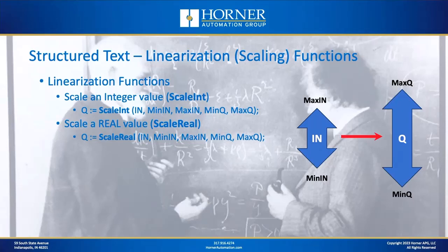So, of course, you can use y equals mx plus b scaling, and we'll show you an example of how to do that. But there also are some specific purpose scale functions available for you to use. There's an integer scale function, and there's a real value scale function. I've got the syntax for those shown on the screen. They're very easy to use, and we're going to demonstrate one of those for you a little bit later.